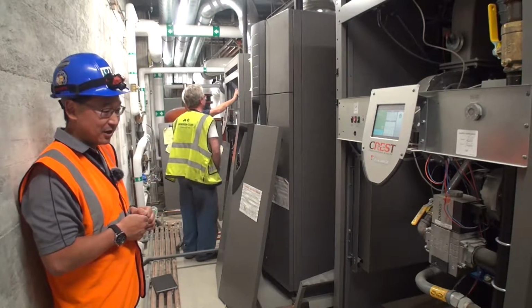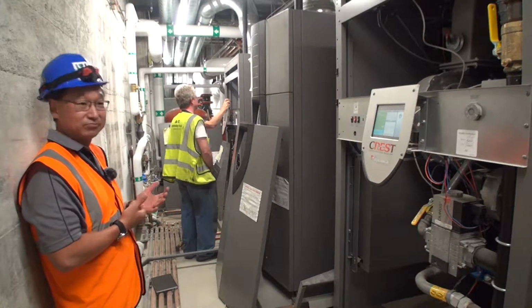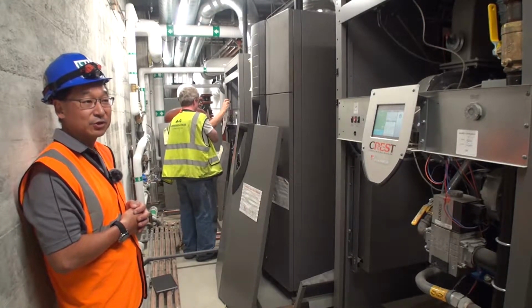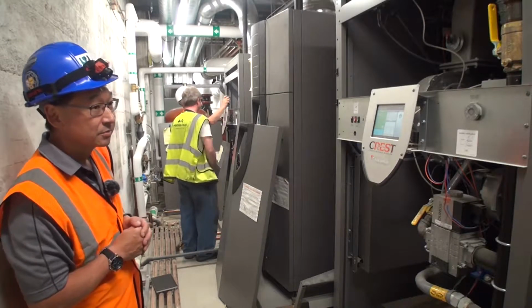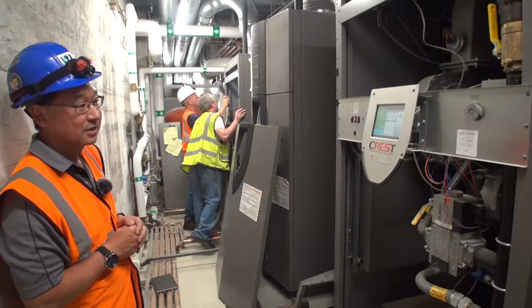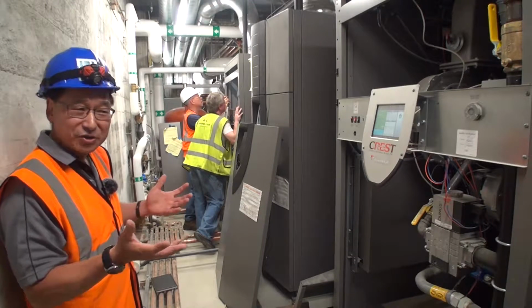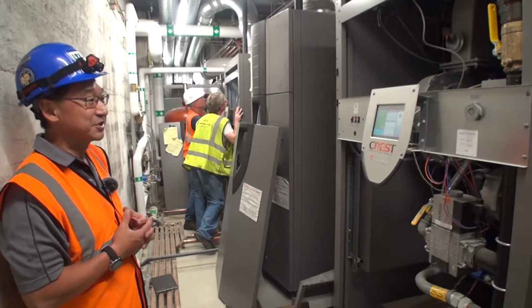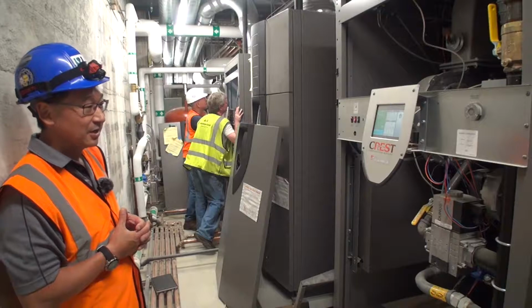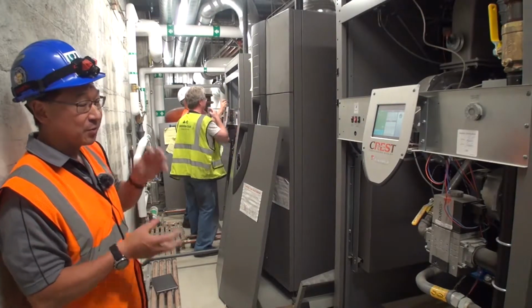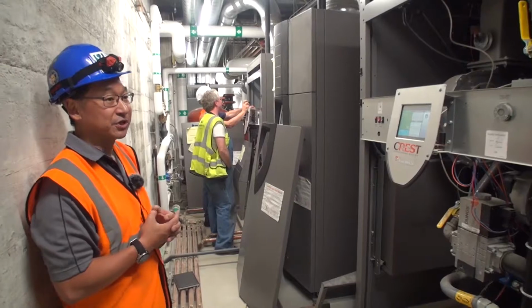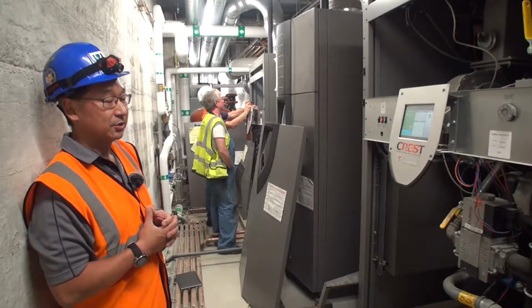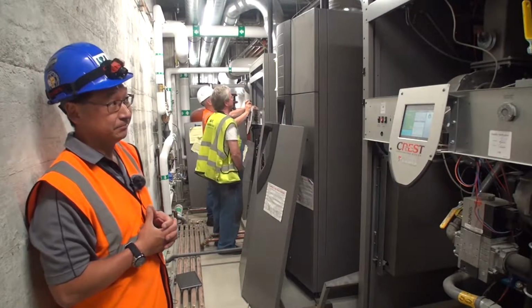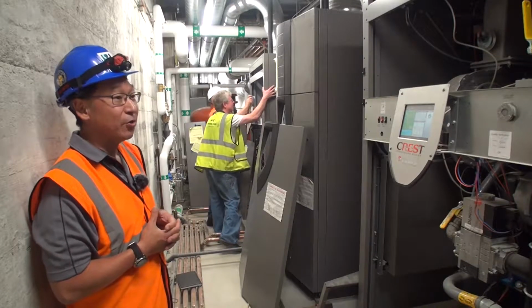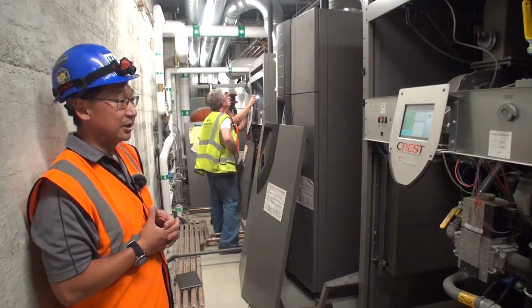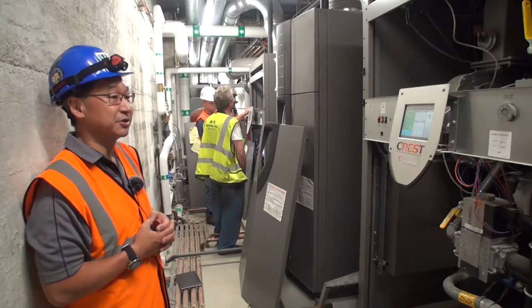But does anyone have any questions on maintenance and what to look for? With no filter, is there anything we need to be concerned about inside? As long as the room's fairly clean, I would say no. There is a procedure once a year to open up the boiler and clean the actual burner itself, if that becomes a problem, but it's a fairly in-depth procedure to open it all up if you need to. Typically, as long as the room's clean, there's really not an issue.